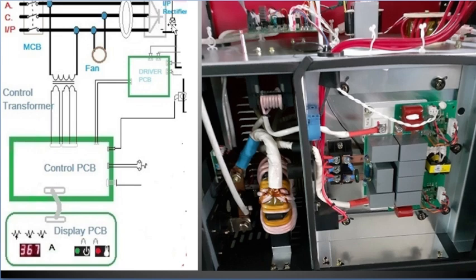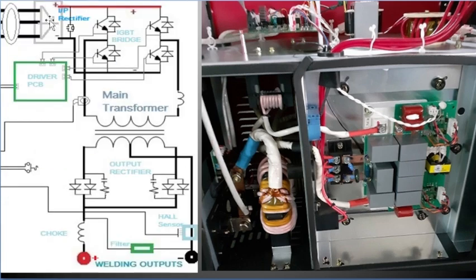The DC bus voltage is connected with a low value of capacitor and resistance. This DC bus voltage is connected to a full IGBT bridge configuration circuit, one with positive, another with negative DC voltage. 2 IGBT modules, each having 2 IGBTs, are connected with a gray driver PCB to a heatsink.